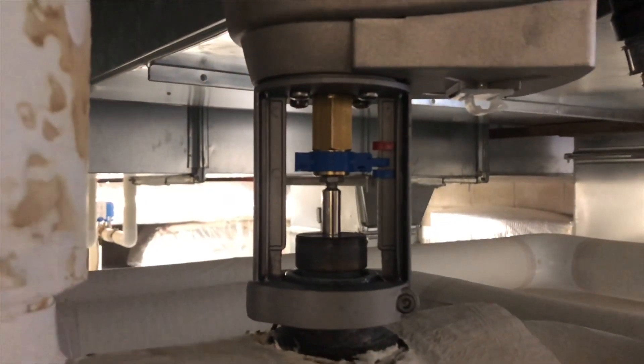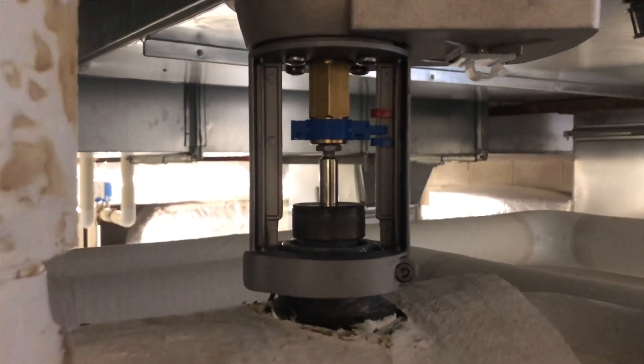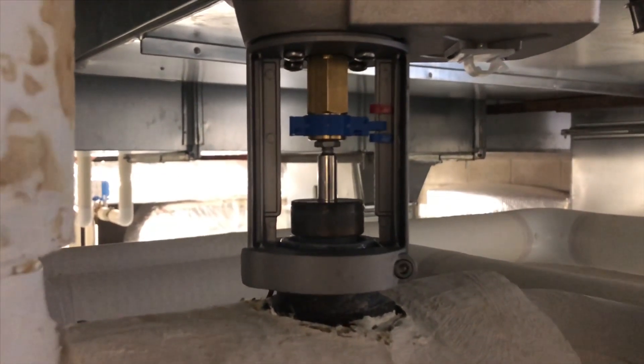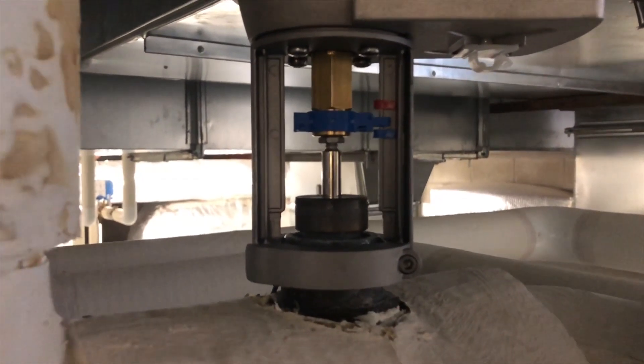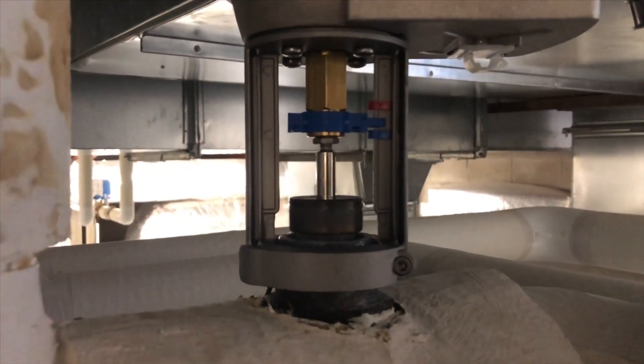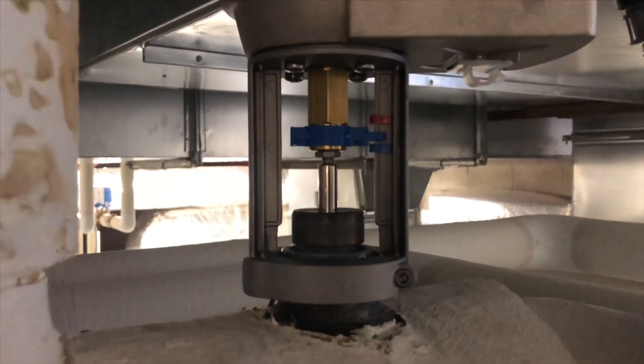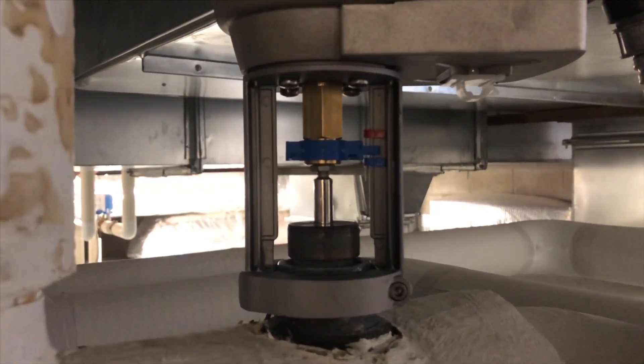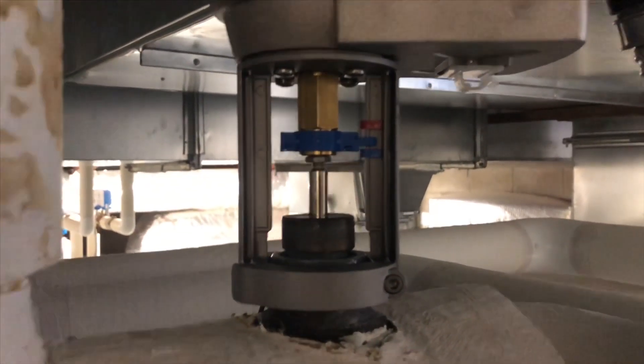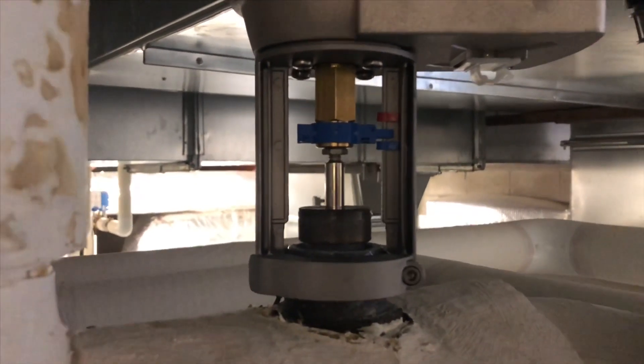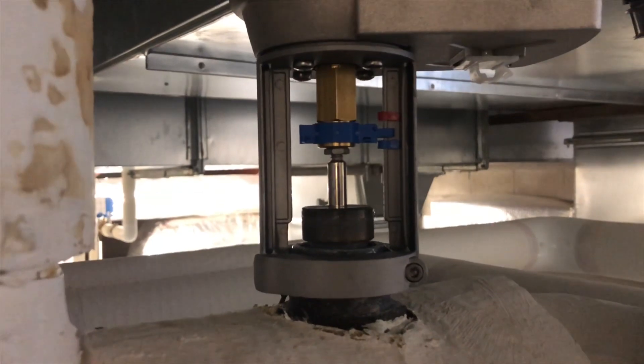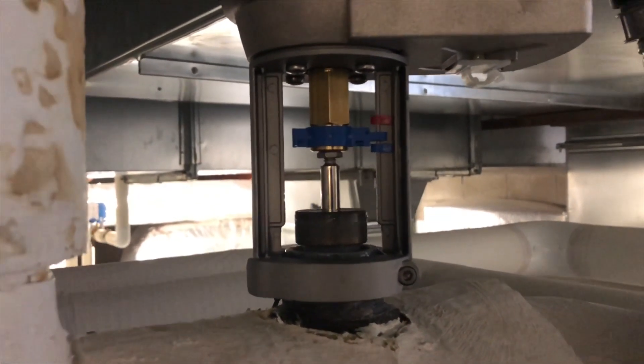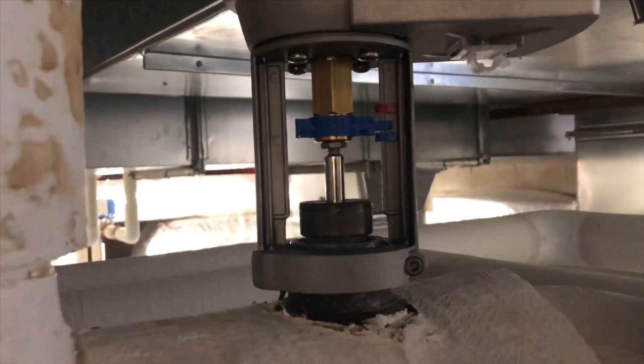On this model of valve, this is a cooling valve. So on this valve, down is open and up is closed. The spring return function on this actuator is spring return up. So closed position on our cooling valve is our fail safe. This valve, when I turn it on, it should self calibrate or it may just go straight to open.